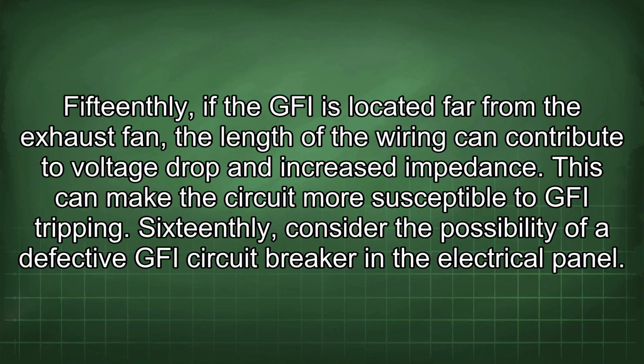15thly, if the GFI is located far from the exhaust fan, the length of the wiring can contribute to voltage drop and increased impedance. This can make the circuit more susceptible to GFI tripping.